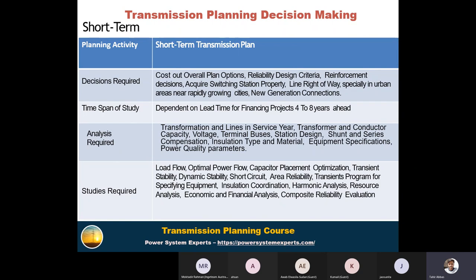So this we will conclude what criteria need to be considered under this planning. Next, the time span of study. This depends on the lead time of financing the project, because in the short term it is only 4 to 8 years ahead, but in the long term the time span is large. So analysis is required. We see the transformation, how much transformation capacity is added, meaning how much demand is added, how much new transformer and new lines are added in the service year, and the transformer and conductor capacity of the existing conductor as well as the proposed conductor for the next 5 years.